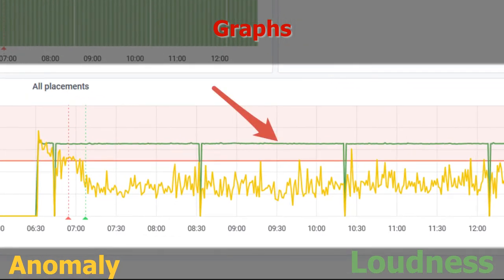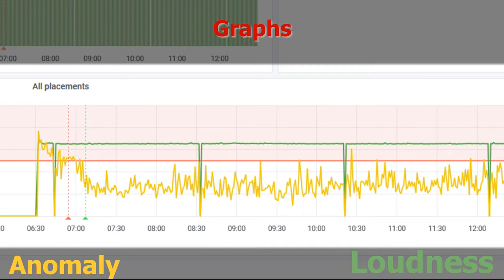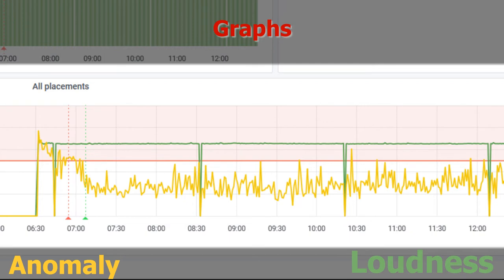The difference between loudness and anomaly is that the loudness graph, shown in green, shows you the intensity of sound that your machine produces. The higher the level, the relatively louder the machine is. Anomaly, shown in yellow, is the certainty of the model that the sound it evaluates is within or outside of its nominal values. If the certainty reaches a preset threshold, an alert is triggered. More data to train the algorithm means more accurate predictions.